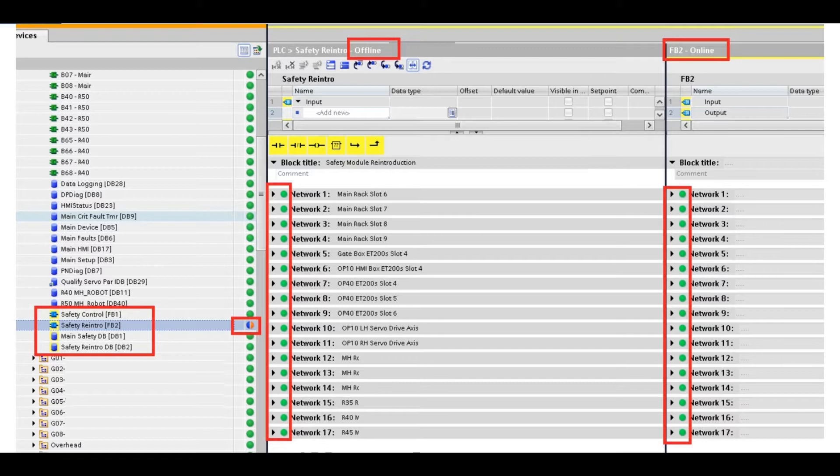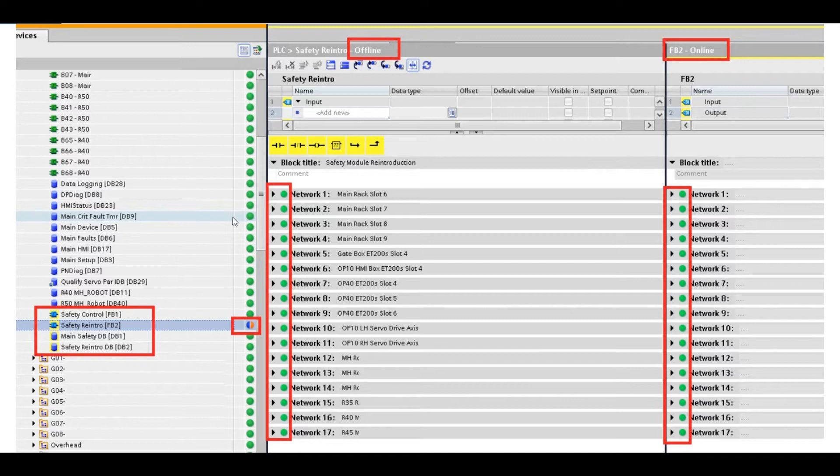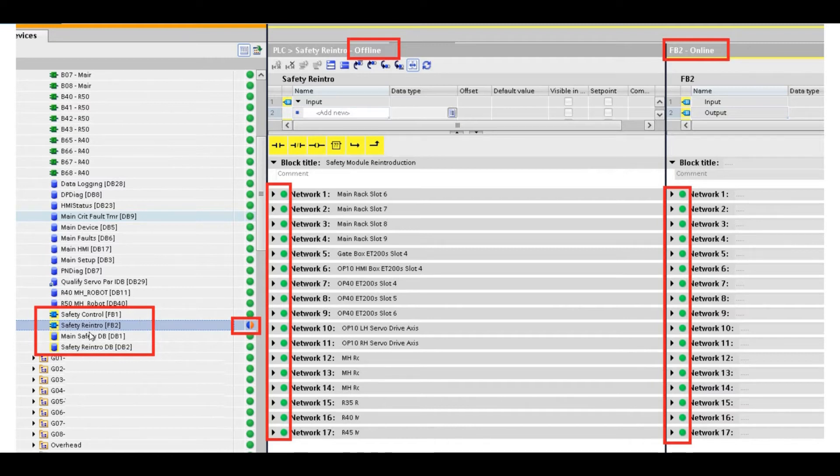But after you compare, even if you only download the standard PLC without any change, without any login to the safety logic, once you download the standard PLC program and go online compare, you find like showing in the picture, all the standard PLC program shows all match because match means green. However, the safety program shows a difference. There are differences inside the safety.